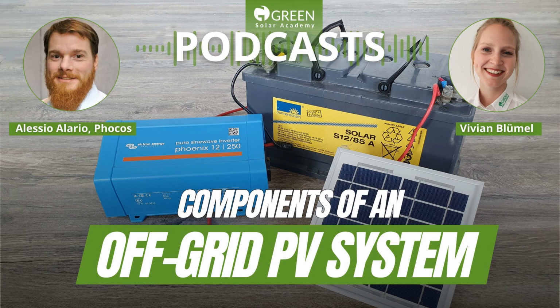Well, essentially you're creating your own small microgrid, and a grid inverter, if your off-grid inverter is compatible with it, you connect it to the same AC power lines as you're using to power your loads. But that inverter, instead of consuming power, will actually feed power from PV through your off-grid inverter into the battery. So essentially you're charging, that's why it's called AC coupled, because you're coupling your PV power on the AC side.